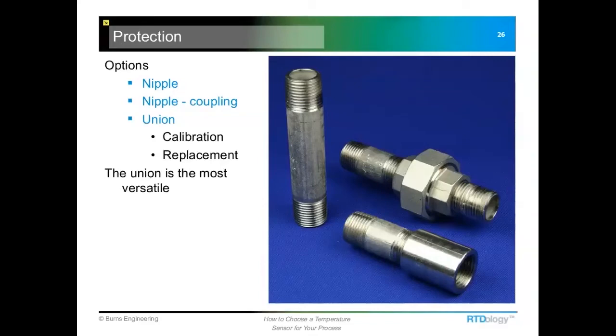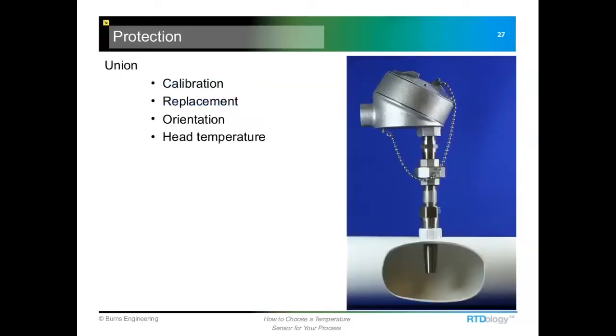When it comes time to calibrate the probe or to replace it, you can just take that union apart and pull the sensor out of the well and stick it in a dry block calibrator and go ahead and calibrate it that way. So it's really the most universal of these, and it's the one that I always recommend. So so far we've got our assembly with our explosion-proof FM connection head on it. We've got the union extension, so we've taken care of some of the maintenance issues.